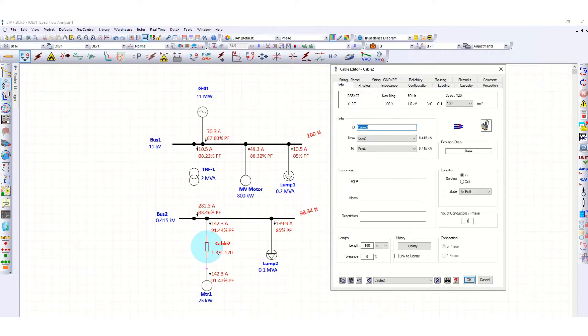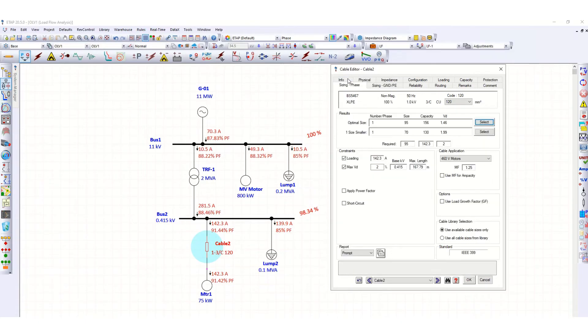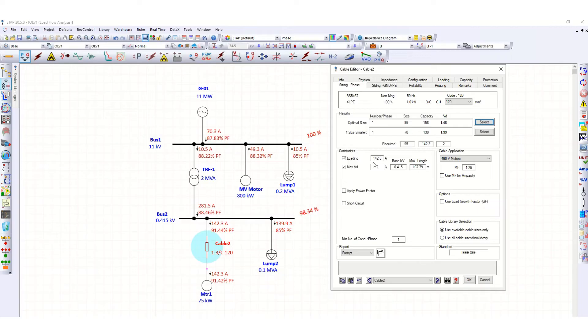The number of conductors is 1 per phase. To size the capacity of this cable, go to the sizing phase tab. Here you can see the loading requirement is 142.3 ampere, and the maximum voltage drop is also shown based on that loading.